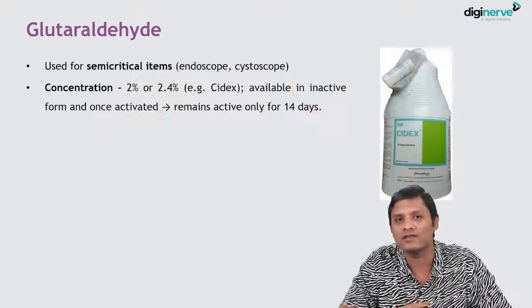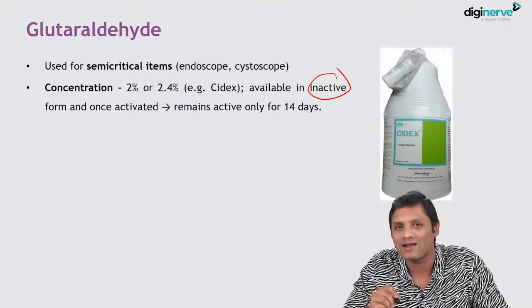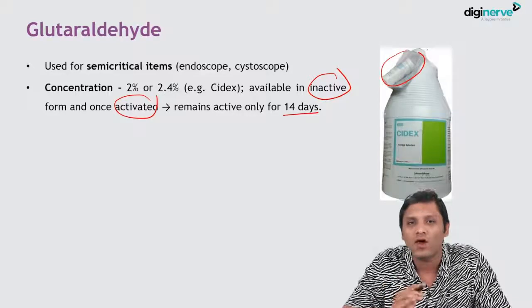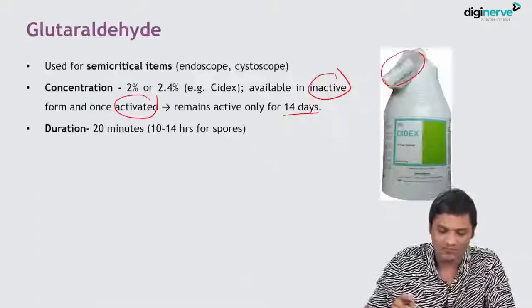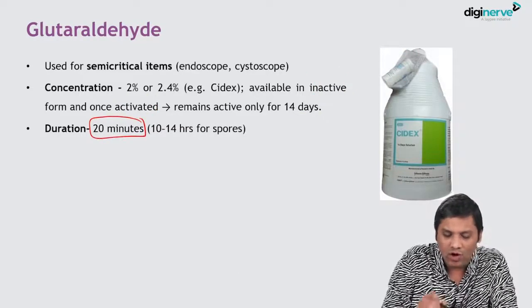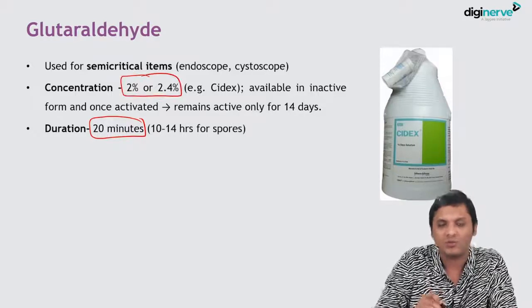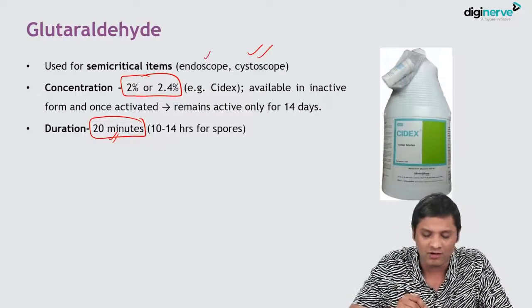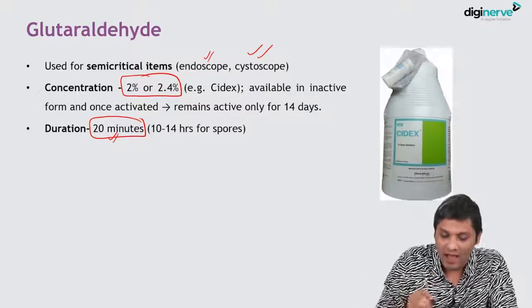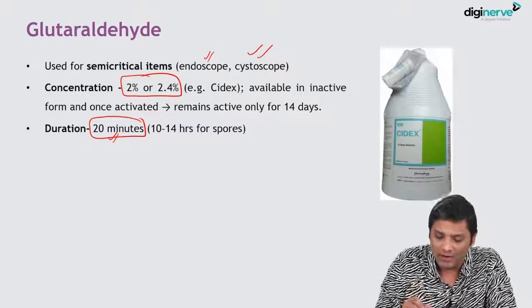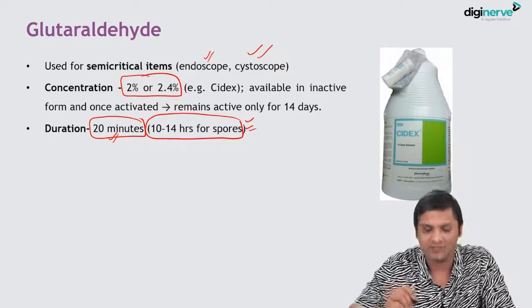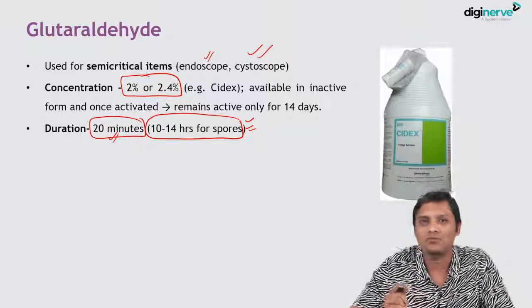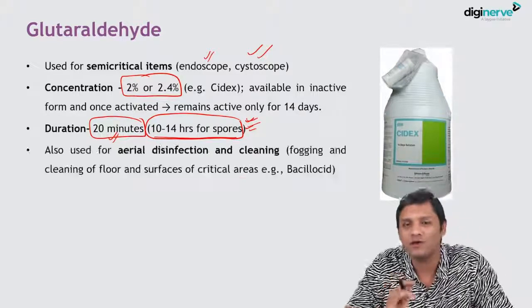A drawback of glutaraldehyde is that it is available in inactive form and must be alkalized before use by adding the activator solution. Once activated, it must be used within 14 days. The duration of disinfection is around 20 minutes at a concentration of 2 to 2.4 percent for high-level disinfection of endoscopes and laryngoscopes. It can also be sporicidal, but for that you must disinfect for a period of 10 to 14 hours.